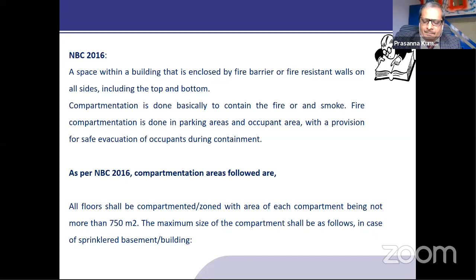To brief on this: up to 750 square meters, we don't need compartmentation as per the code, since fire can be controlled or extinguished within that area. Above 750, up to the different areas given in the table, a minimum of 2 compartments is required—there's no such thing as a single compartment. For example, for a business class building with 3000 square meters, from 750 to 3000 we need a minimum of 2 compartments, and above 3000, one additional compartment is added for every 3000 square meters.